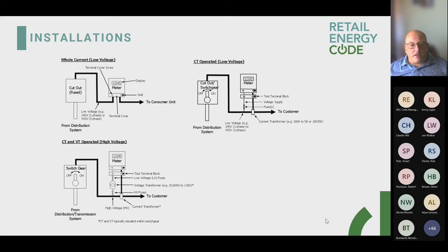The difference with this type of metering is all the electricity flows through the meter. Now it only shows one cable here, but there are four cables - two coming in and two going out, live neutral going in, live neutral going out. I'll show you that in a bit. But for simplistic terms, the main thing to remember with this type of metering is that in effect, all your electricity goes through the meter. So there's no way of bypassing this without doing something illegal. If the customer pulls the main fuse, the meter goes off, the customer's equipment goes off. Exactly the same thing if they take the meter off - that's it. That system shouldn't operate unless they bypass it, but the meter will stop registering, and that's how that works.